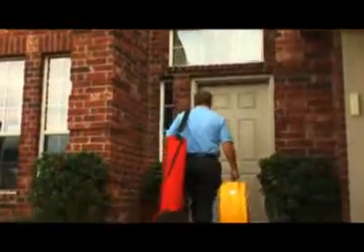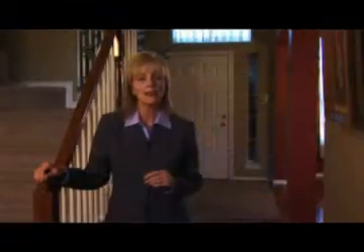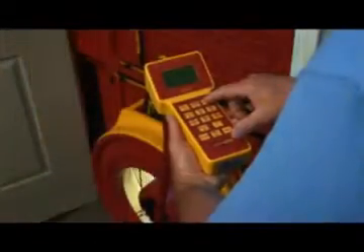The first step is to get a Home Duct Performance Test. The process begins with a short interview of the adults living in the home. Next, your consultant will perform a series of inspections and tests. The primary test measures how leaky your home and ductwork are. This is done using a computerized diagnostic instrument called an infiltrometer blower door.